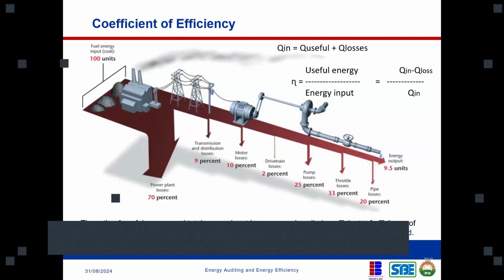Now there's a way to optimize the use of a pump, which could include the use of variable speed drives on these motors, and some other things. We'll talk about that when we get to energy efficiency in pumps. But you still have about 25% loss, and in some cases you might have valves to throttle or reduce the pressure.